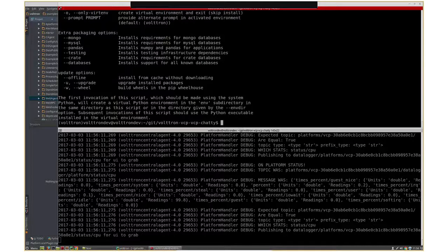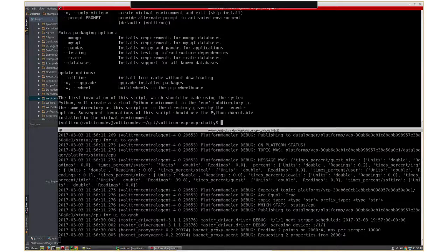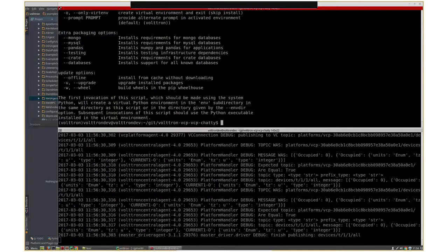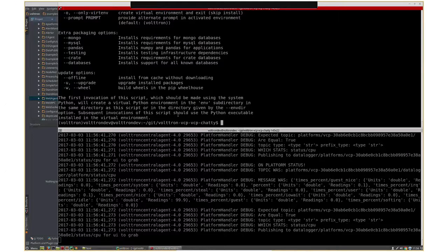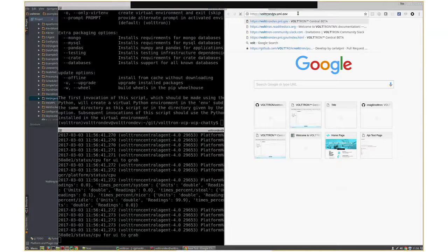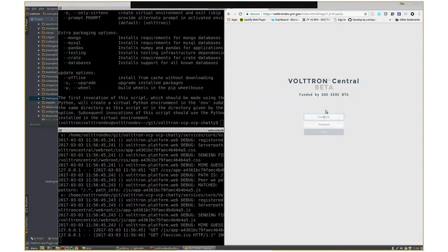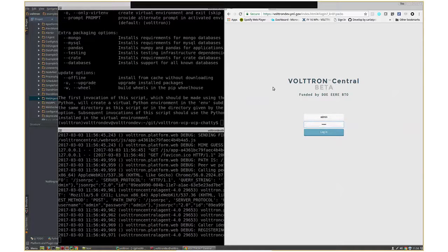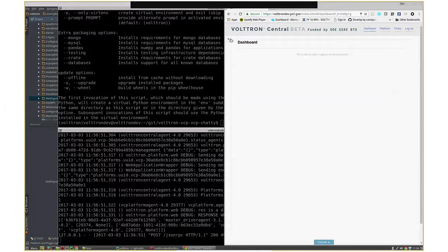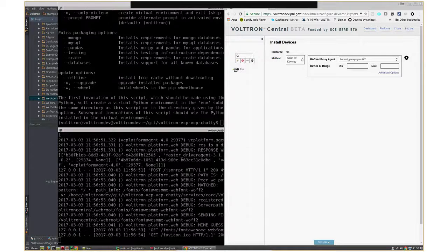Now the number of points per device, that was the earlier conversation about 100, right? Yeah, that's kind of your high watermark for how many points per request you're going to get. Even without the segmentation bug, if it does support segmentation, the proxy still has to divide that request up itself automatically. When you filter down to the points that you actually want to subscribe to, it would rarely exceed 100, in my experience.